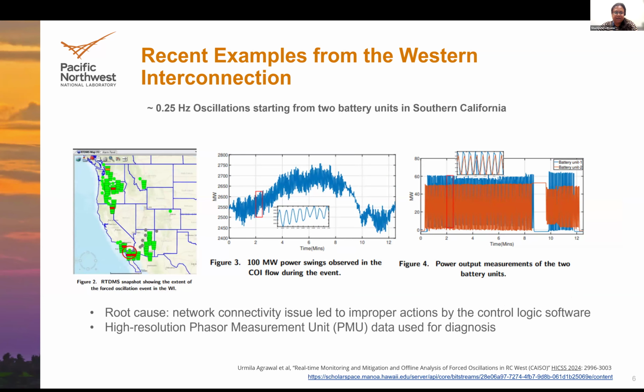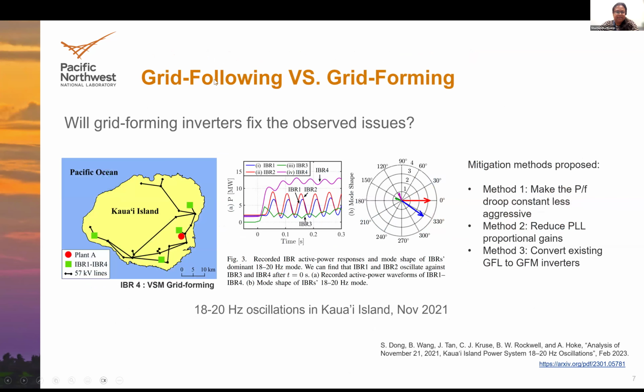Similarly, again, a battery plant introduced around 0.25 hertz oscillations from Southern California. So here, this is the RTDMS snapshot that CAISO had. So the source region was in Southern California, but it showed up throughout the system. And basically due to interacting with, again, the North-South A mode, the oscillation which generated in Southern California propagated throughout the entire interconnection. And the root cause here was some network connectivity issue leading to improper actions by the control logic software. In both of these cases, the inverters were grid following.